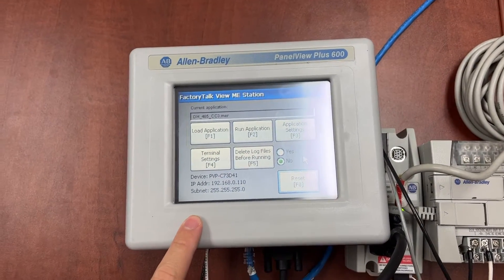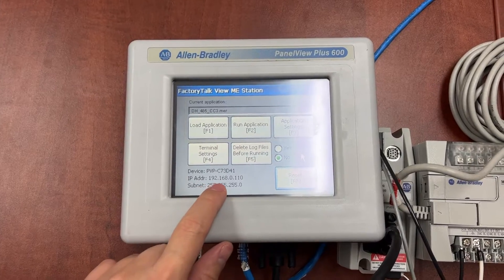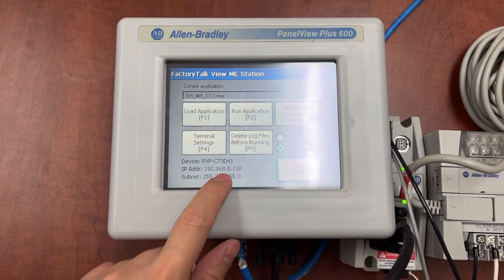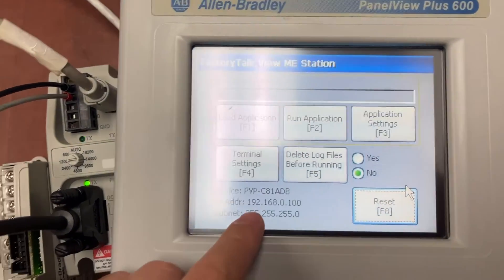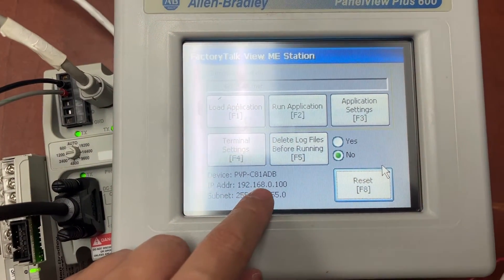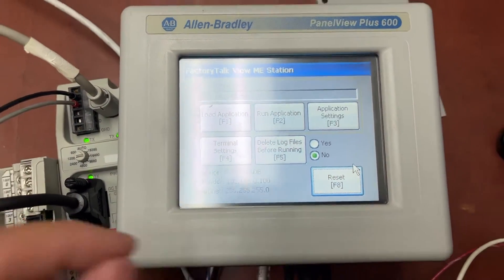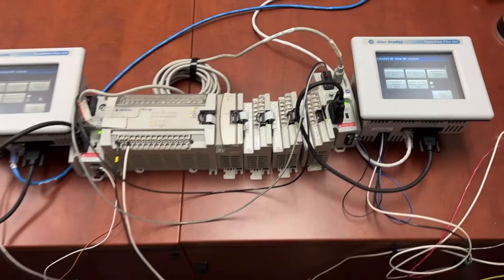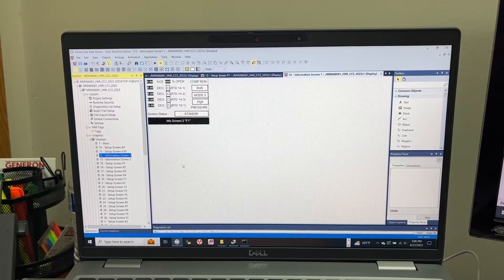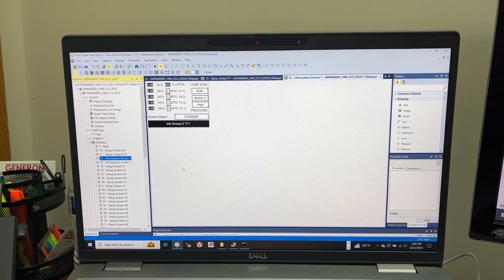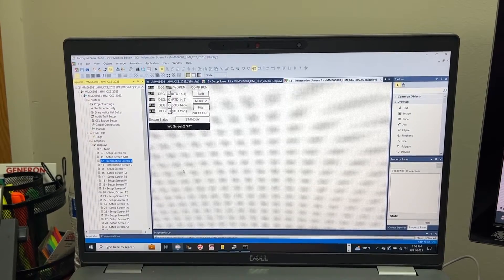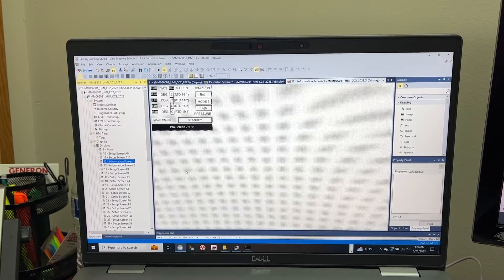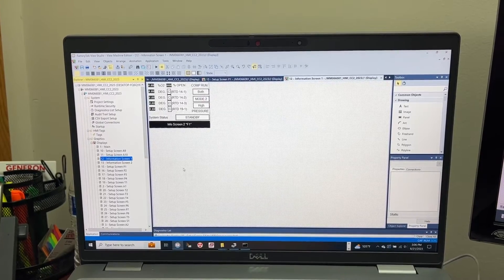The IP address for this one is 192.168.0.110, and the other HMI IP address is 192.168.0.100. In Factory Talk View Studio, we will have to create two separate MER files. Each will have a unique node number to set to the HMI.